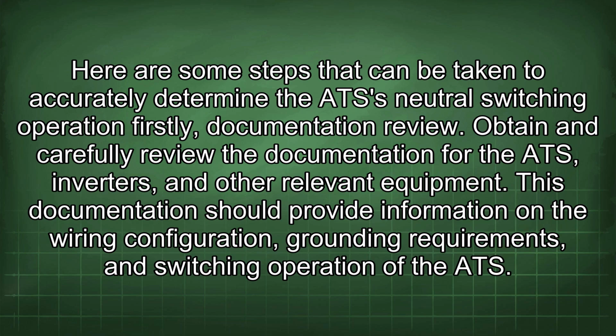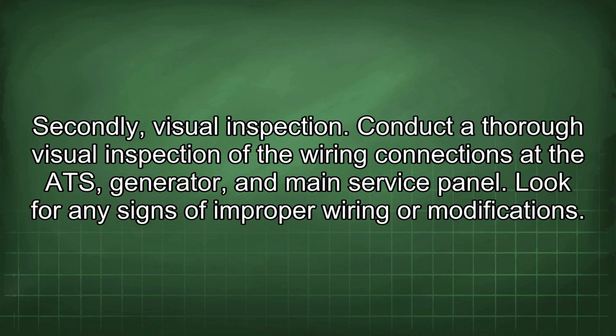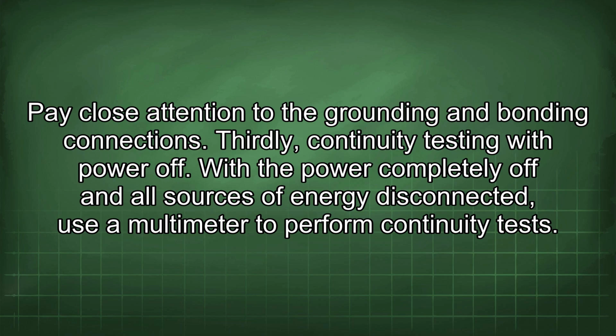Firstly, documentation review. Obtain and carefully review the documentation for the ATS, inverters, and other relevant equipment. This documentation should provide information on the wiring configuration, grounding requirements, and switching operation of the ATS. Secondly, visual inspection. Conduct a thorough visual inspection of the wiring connections at the ATS, generator, and main service panel. Look for any signs of improper wiring or modifications. Pay close attention to the grounding and bonding connections.